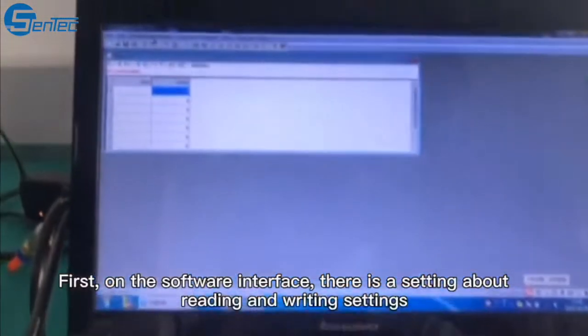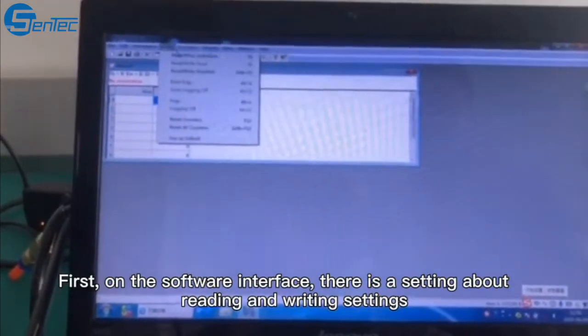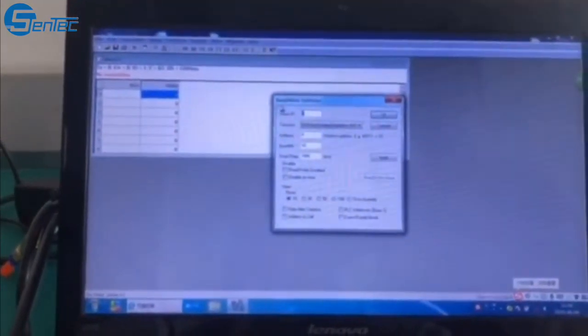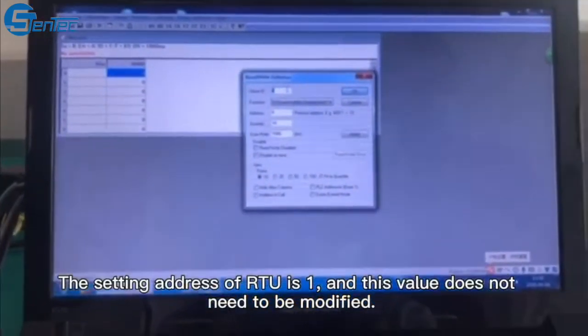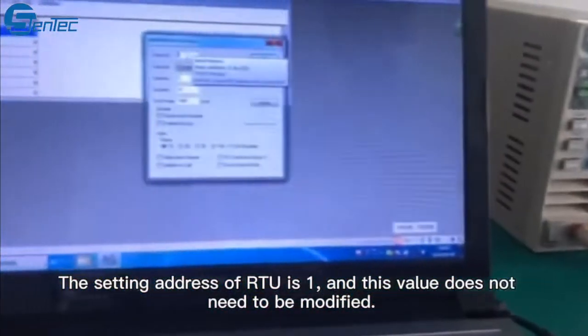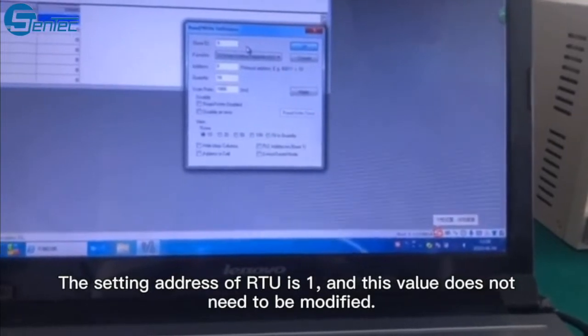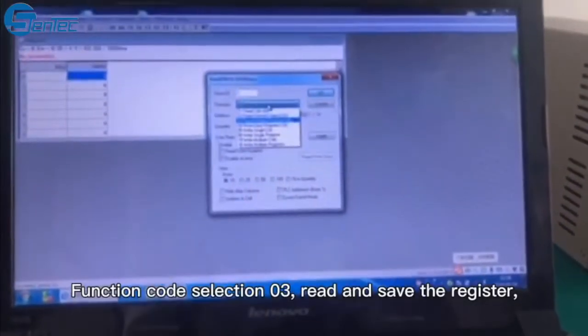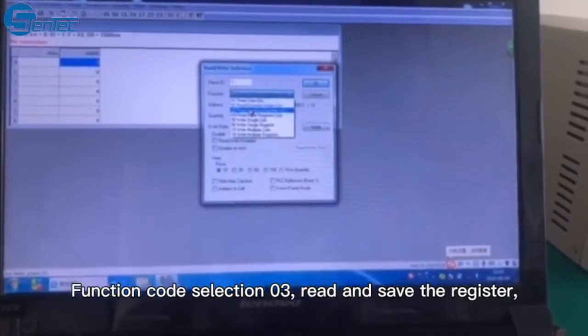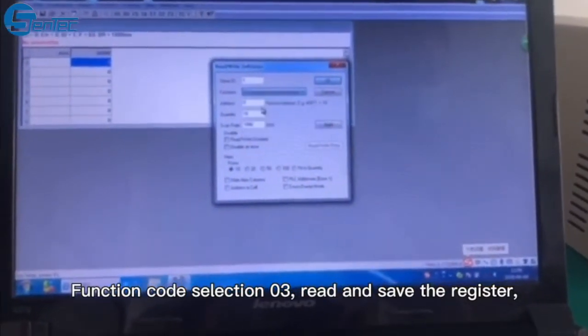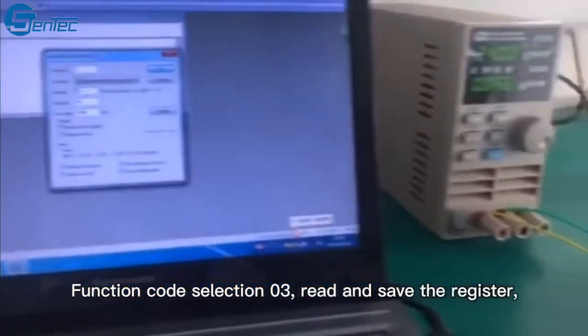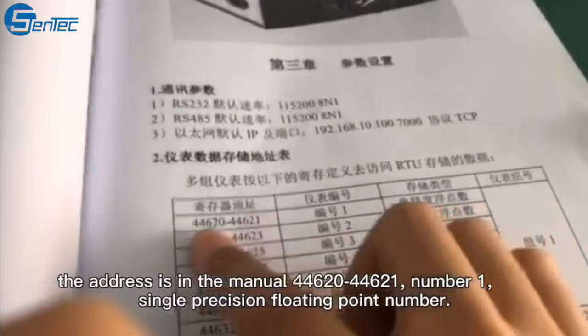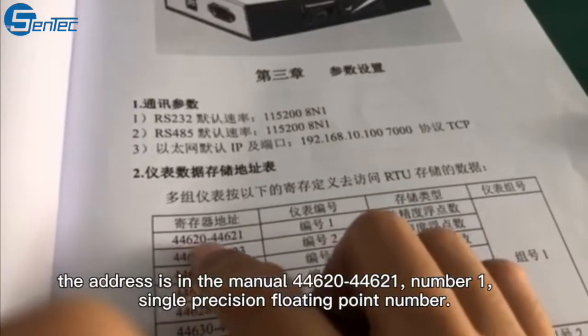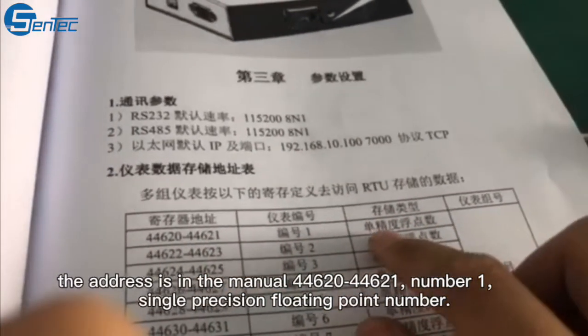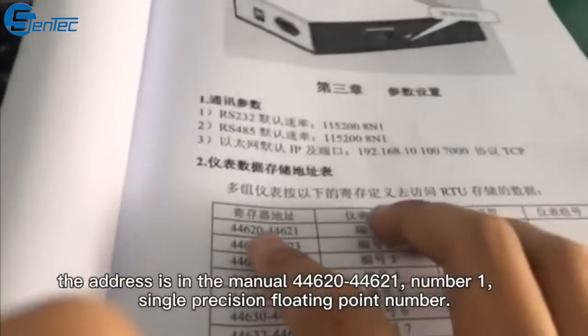First, on the software interface, there is a setting about reading and writing settings. The setting address of the RTU is 1, and this value does not need to be modified. For the function code, select 3, read holding registers. The address is in the manual: 44620, 44621, number 1, single precision floating point number.